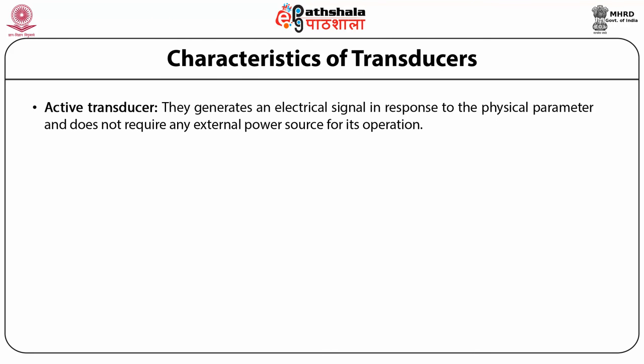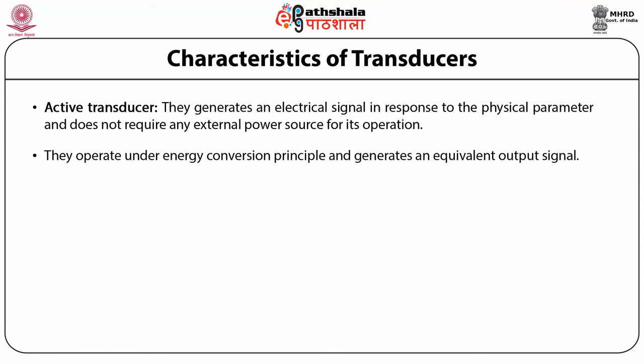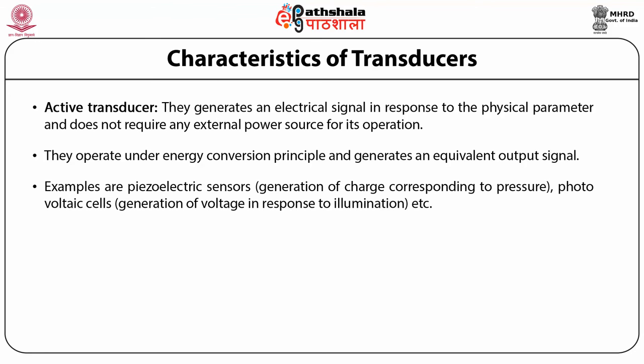There are two types of transducers — active and passive. An active transducer generates an electrical signal in response to the physical parameter and does not require any external power source for its operation. They operate under energy conversion principles and generate an equivalent output signal. Examples are piezoelectric sensors — that is, generation of charge corresponding to pressure — and photovoltaic cells, which generate voltage in response to illumination.